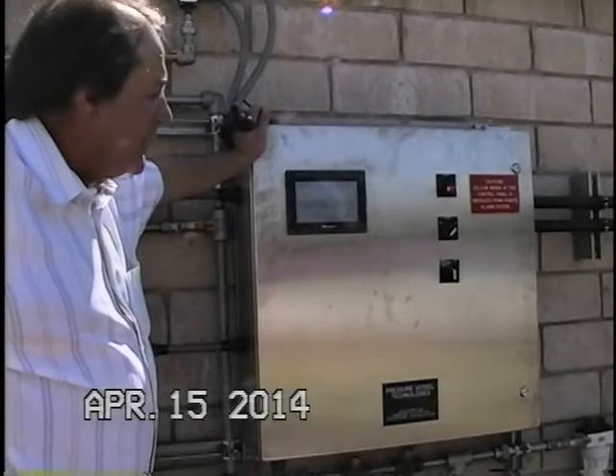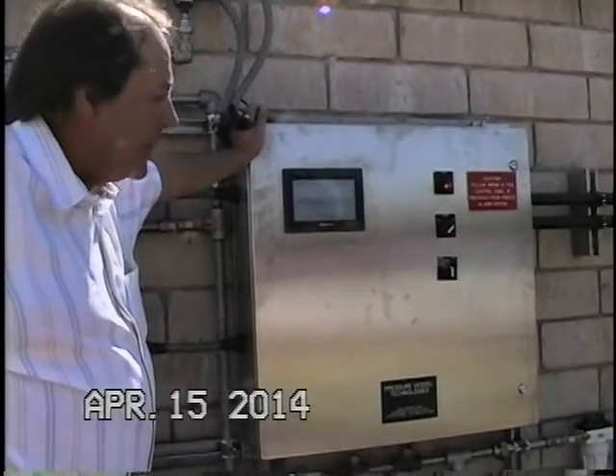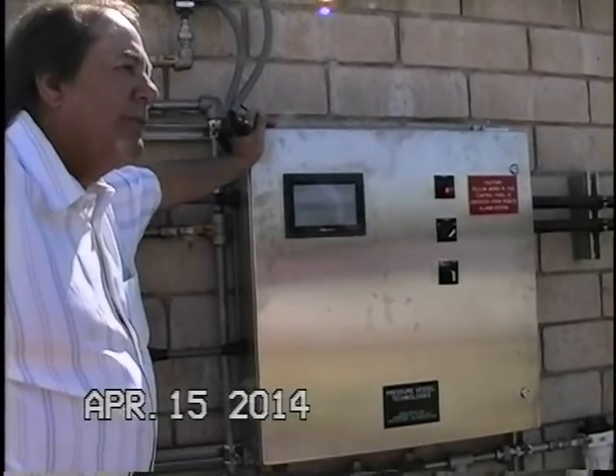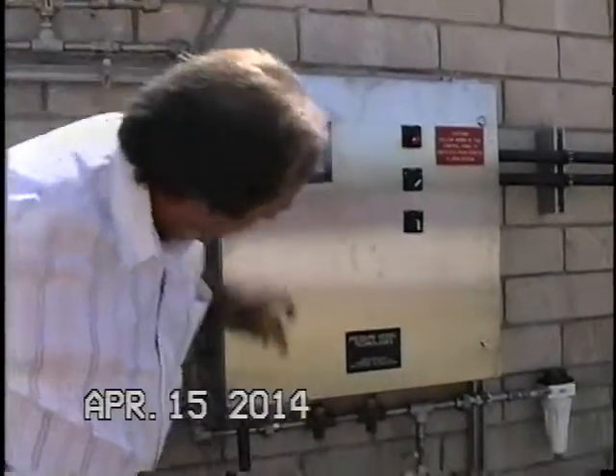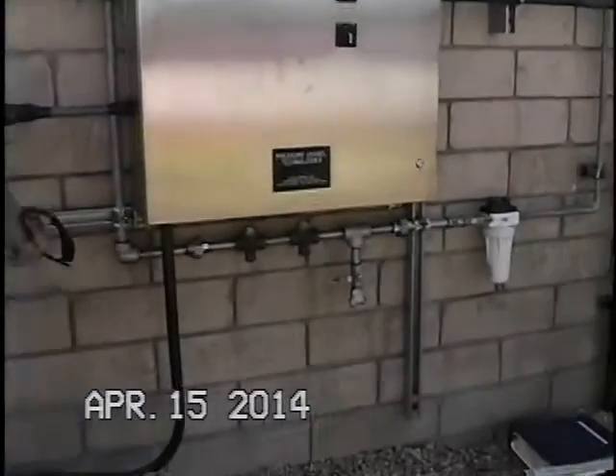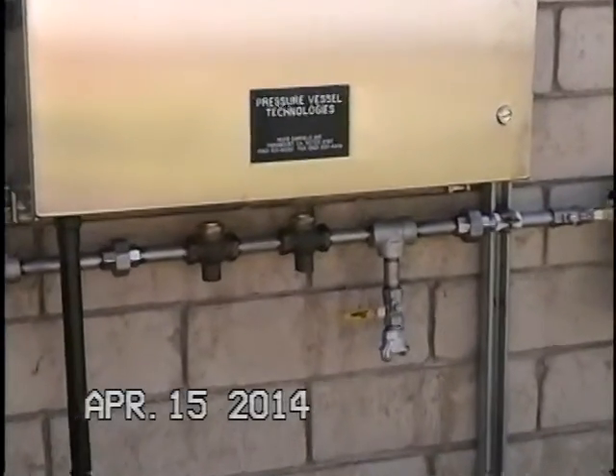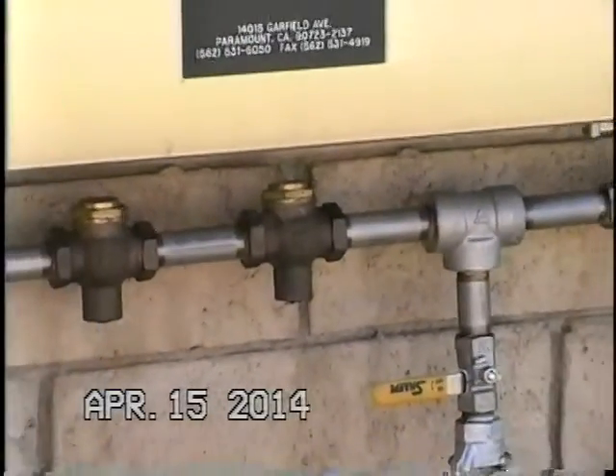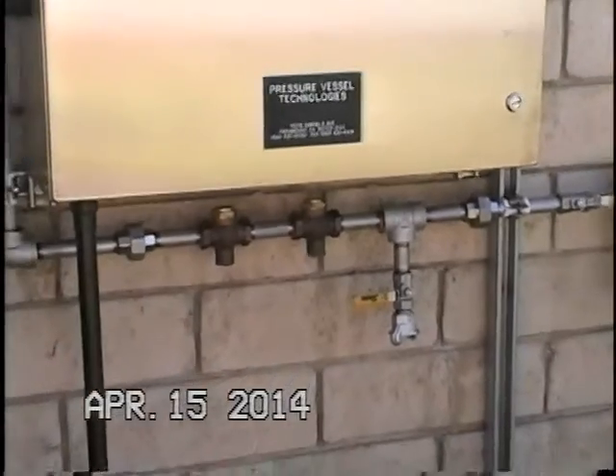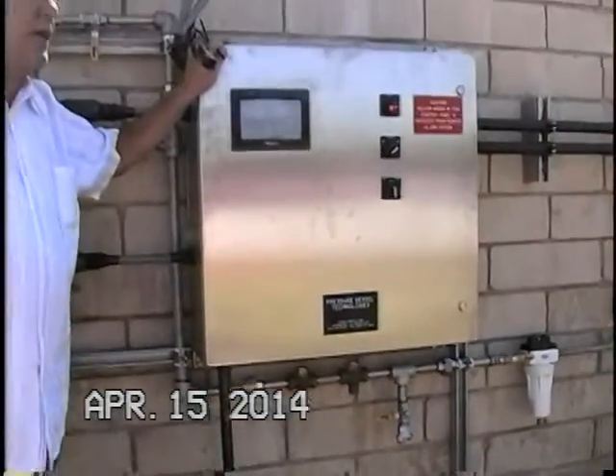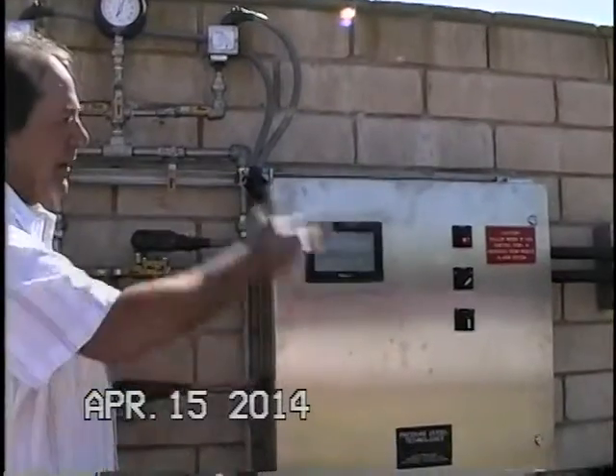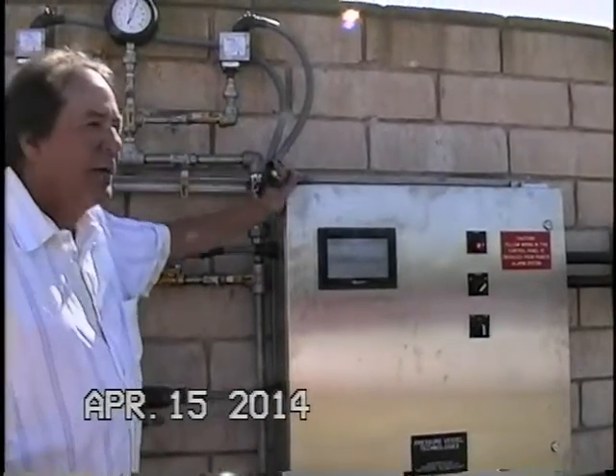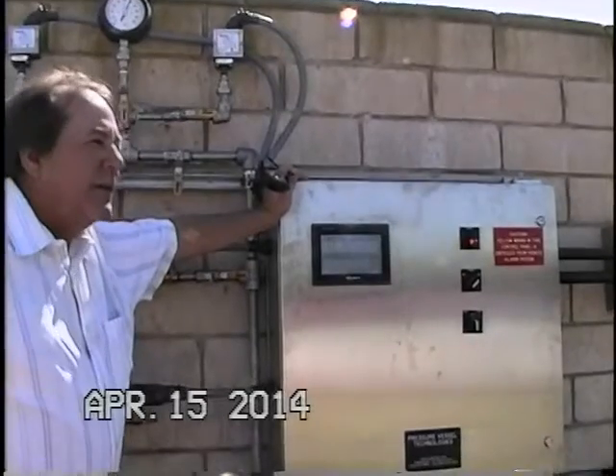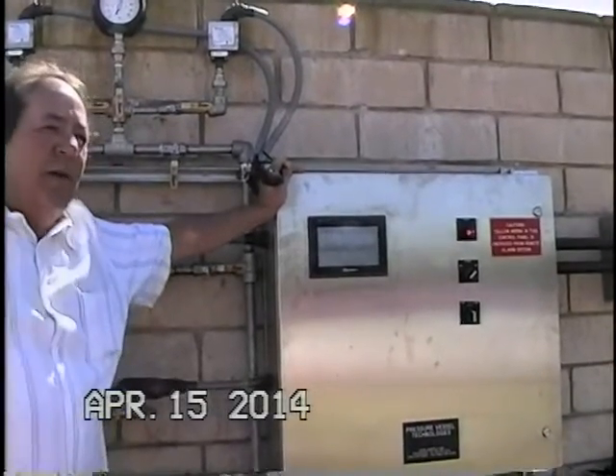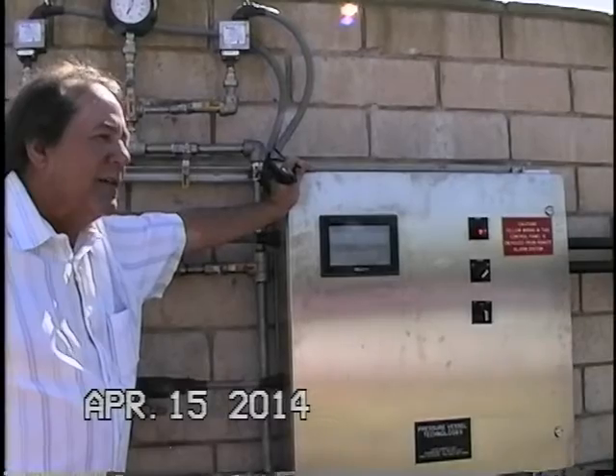In this particular case, you've got basically almost the same as you would in a potable water system. And then the two that are underneath the panel there, these are check valves. In case we had a leak between here and there, you're not emptying out any of the air volume within the surge tank. That is there as a protective measure in case someone left a valve open, there was a pipe failure, there was a leak, something along that nature. But that way we maintain the air within the surge tank.